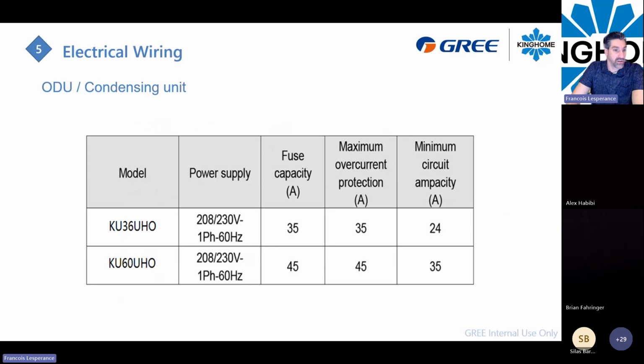So for the outdoor unit, we said we have only 2 different cabinets, the 3-ton and the 5-ton. The maximum overcurrent protection for the 3-ton is 35 amp, so a 30 amp breaker is high enough to protect the system.